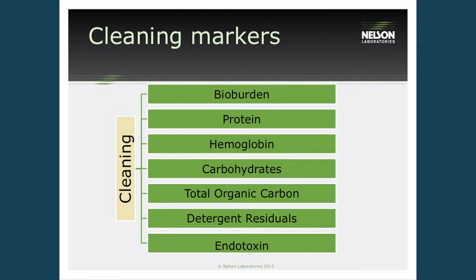But we also need to think about how the device is used in the hospital setting. If the device is going to come into contact with cerebral spinal fluid, we want to make sure that we're testing for endotoxin. If the device comes into contact with any sort of blood, even if it's just nicking mucous membrane and that sort of thing, it's always good to test for hemoglobin. And the top marker that the FDA is looking for is protein. So, if we're just doing an overall very basic approach to a cleaning validation, we always recommend to test for protein and hemoglobin first, and then testing the other components depending on how the device is utilized and where the testing is going after that.